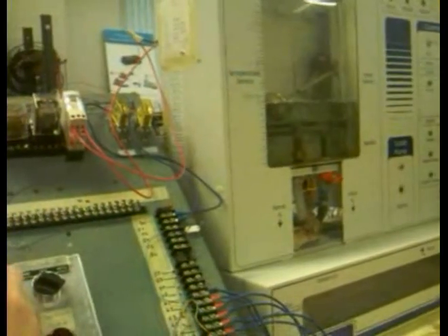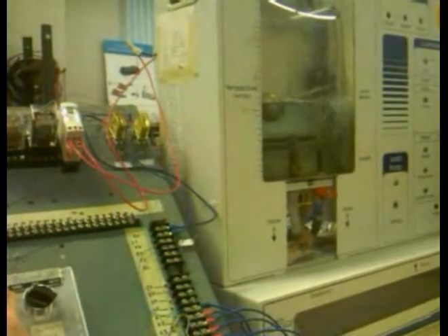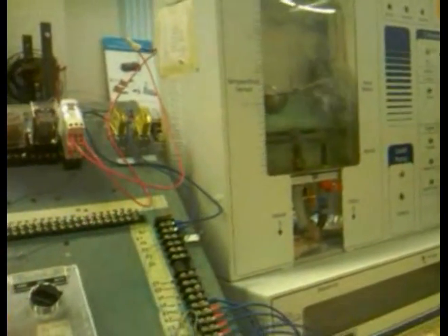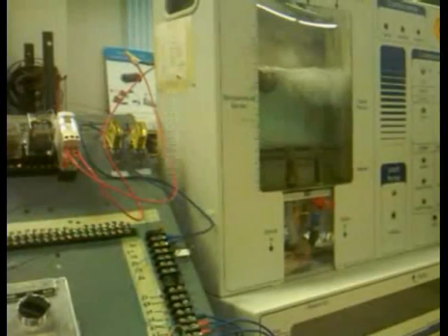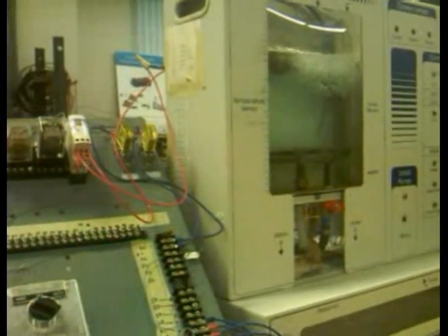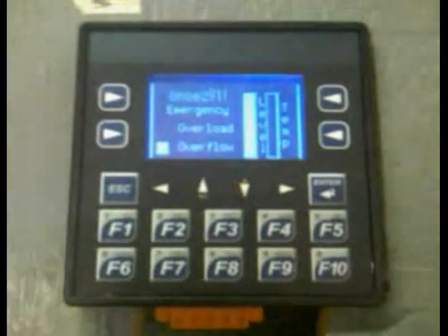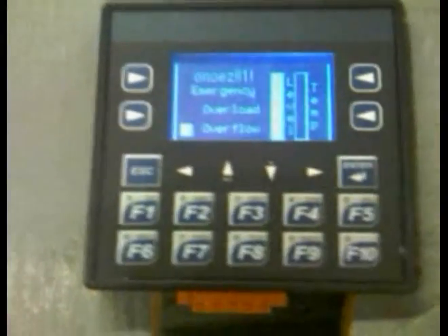And you see the two pumps running right there in manual mode, one at a time, and then I'll turn them both on, and then we're going to test the overflow. There's actually a protection on it that once the tank hits a certain level, it's going to hit the emergency stop, as you can see right there.